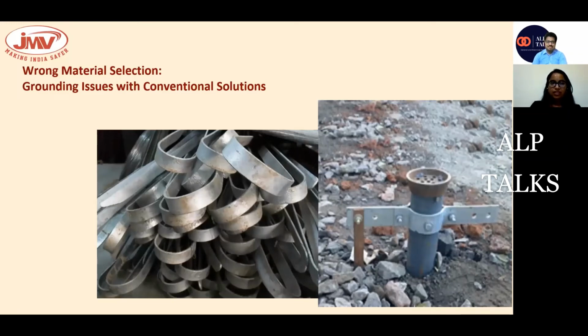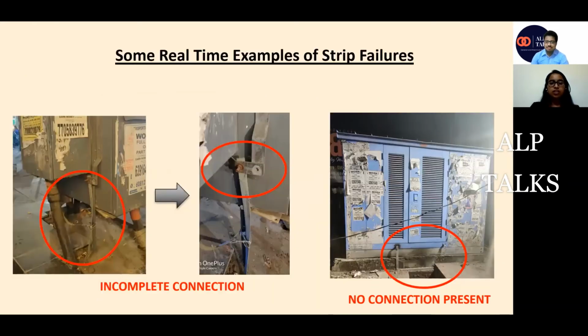Similarly, for the strips also, I have seen many incomplete connections on different sites whenever I have visited. I have found that people are using strips for the interconnection of equipment through the earthing. But after some time, because they have used nut and bolt, as you can see in the pictures, which are real-time pictures I have taken for my reference, the nut and bolt gets loose. Either they corrode after some time, or they get loosened up and are not even available at the site. Due to this also failures happen, because if my equipment is not connected properly with the earthing system, the earthing will not serve its purpose and the equipment will not be safe.